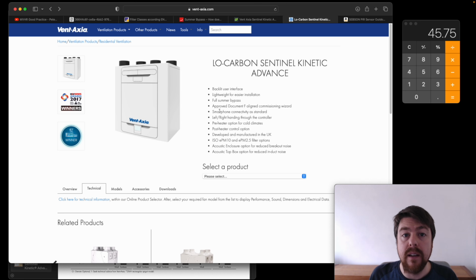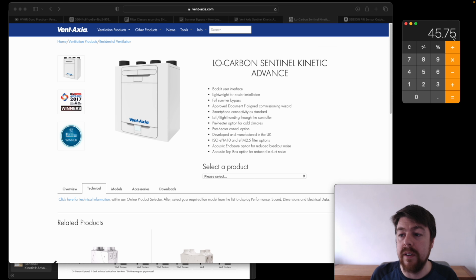So then the only thing was to choose the right size. Bear in mind, we figure we have around a 45 to 46 litres per second requirement. Here is the Vent-Axia catalogue, and since you never want to oversize your plant, the smallest size comes in around 68 litres a second, from what I can ascertain, at 100 pascals. That's a bit more than I need, but it has a VSD and ramps down, so I'm fine with that. That's the unit I wanted.